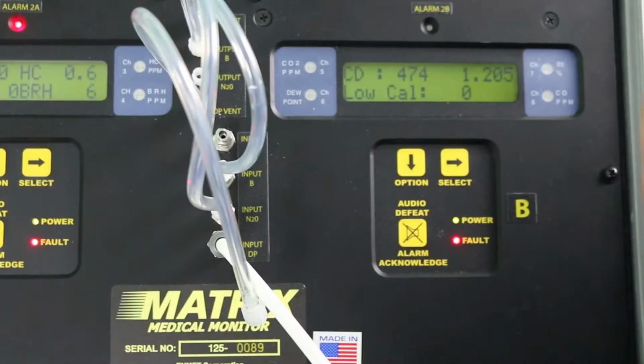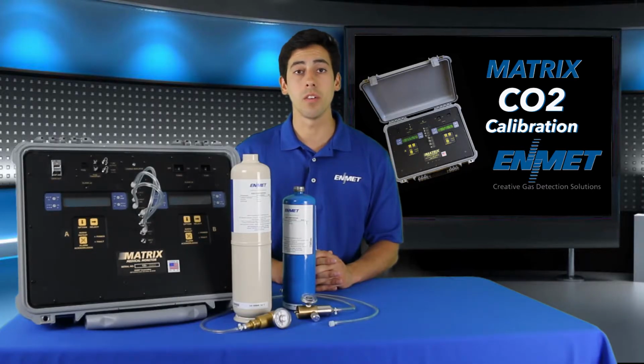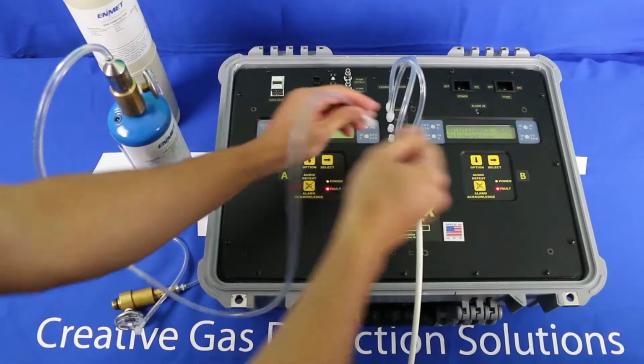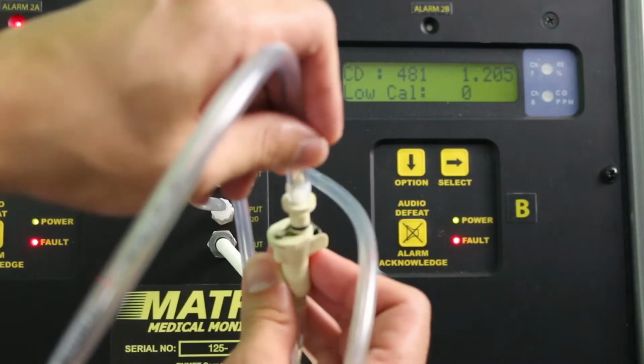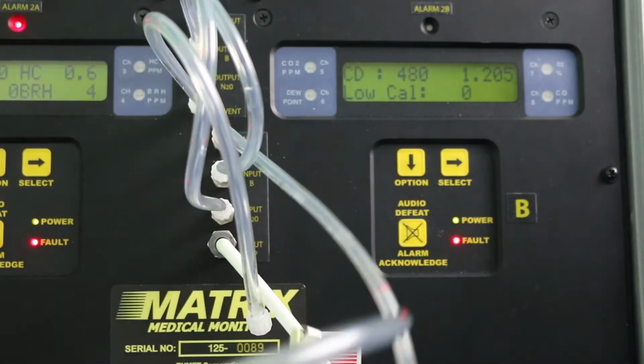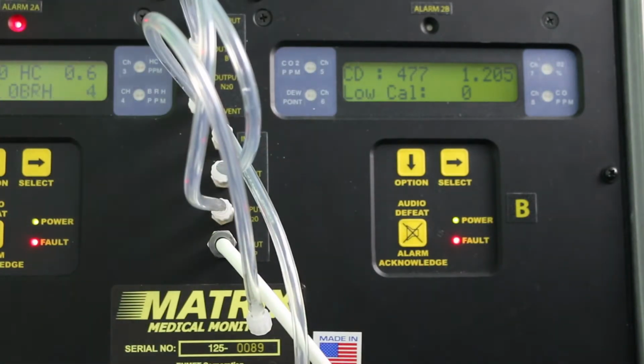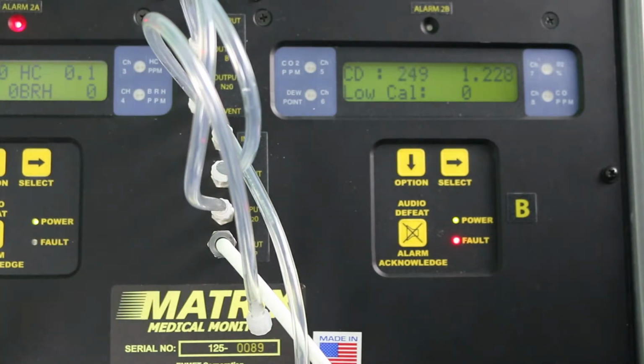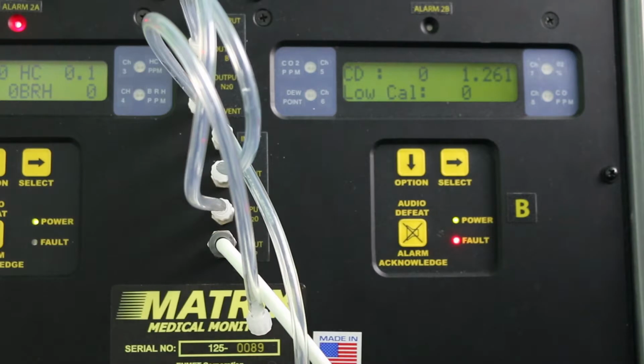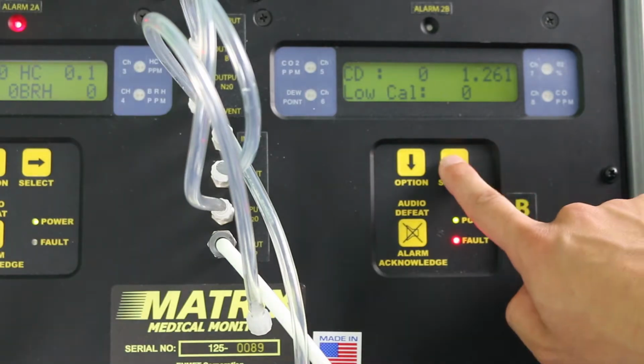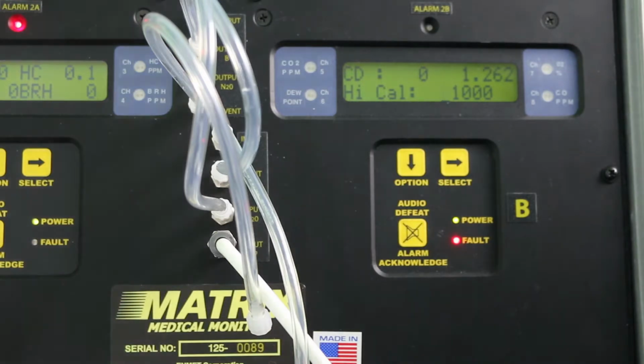For the calibration of CO2, we are able to hook up to input A because CO2 does not affect the other sensors. You'll need to remove the original hose and connect the CO2. The present CO2 value should now be decreasing. This is a negative going sensor, so the raw sensor signal will be inversely proportional to the concentration of CO2 applied. You will need to wait for the voltage output from the sensor to stabilize, which will take about 2 minutes. Once stable, you can press Select to accept the low cal and enter the high cal.